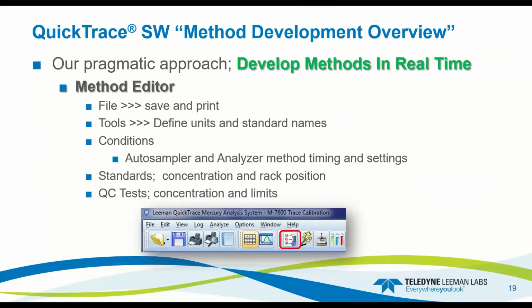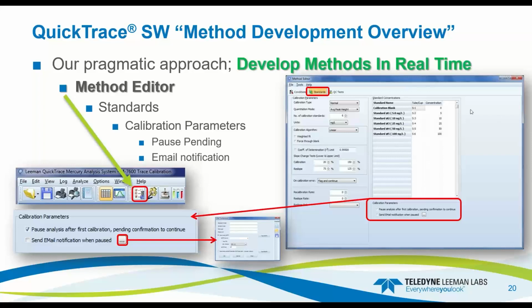Method development. So we develop methods in real time. In the Method Editor, you have tools where you can define the units, standards, conditions, your auto sampler, and your analyzer timings and settings. Enter your concentrations and rack position for your standards, and then your QC test concentrations and limits. This is all here under Method Editor. And then from there, it looks like this. So it'll enter your standards. You can pause at the end of the calibration if you want. You can have the system send you an email when it's done with the calibration. There's a number of things that you can do in here with Method Editor.